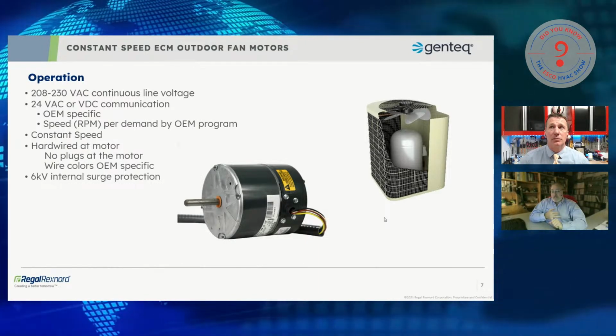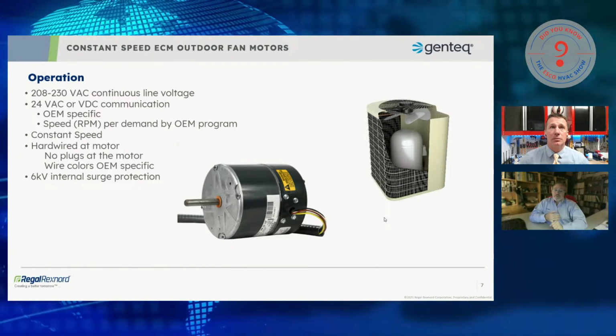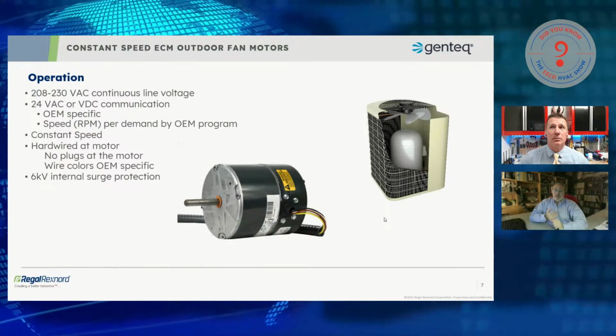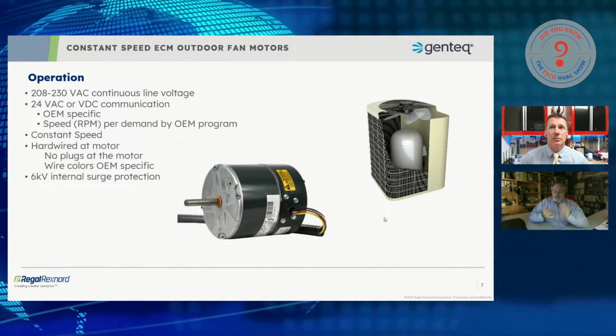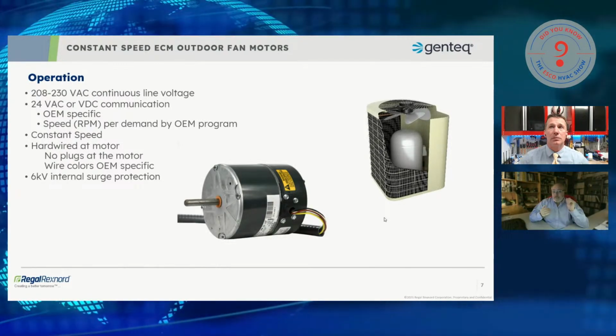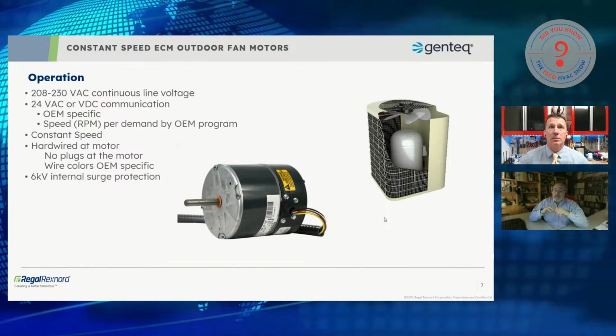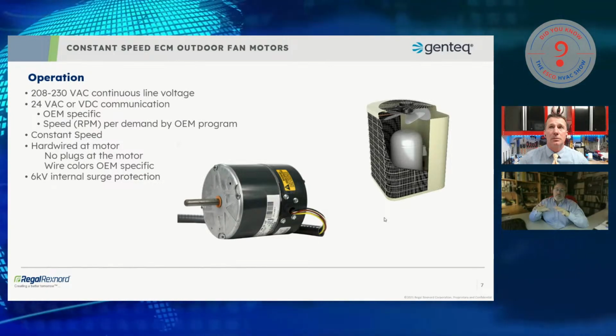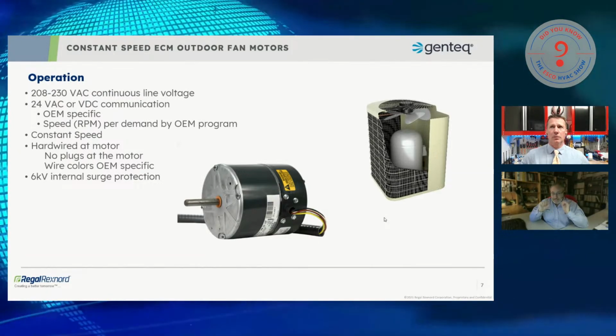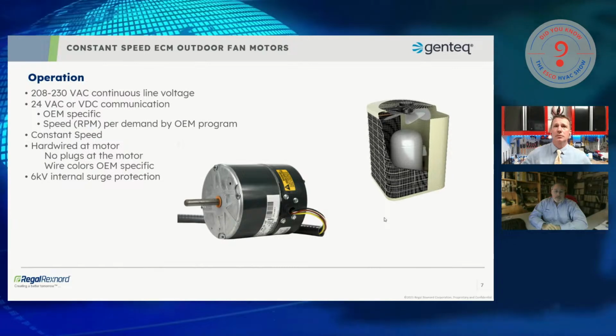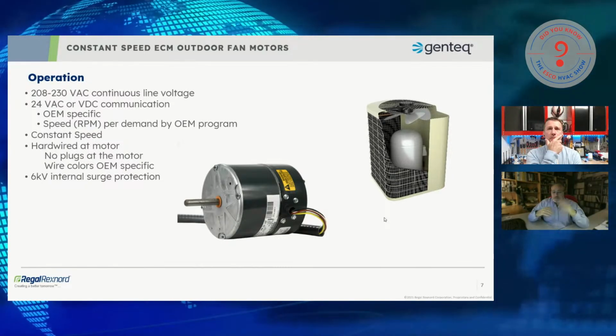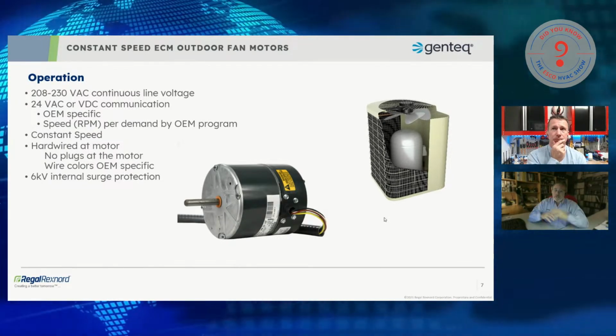If I didn't mention, and this is very different than our indoor blower motors, this is a constant speed motor. So this motor doesn't care about how much torque it's operating at. It doesn't have a constant airflow algorithm. It's just told to operate at a given RPM, and that's all it does. It operates at that RPM all the time. It doesn't try and speed up or slow down to maintain an airflow operating point.